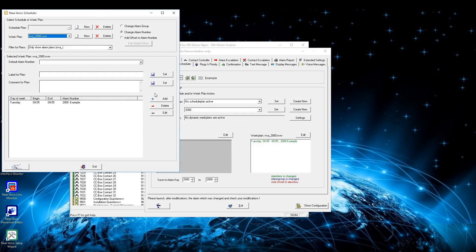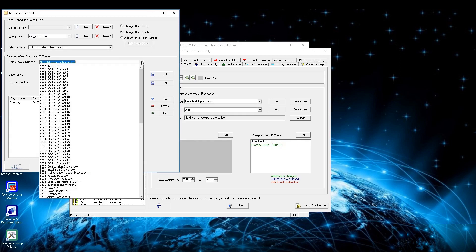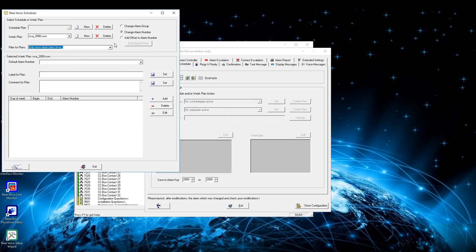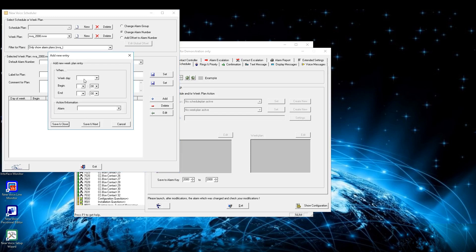On top of this window you can define what should happen — either the group changed for this alarm, the alarm number changed, or an offset added to the alarm for launching. By the drop-down menu default alarm number you can define what alarm number should be launched if the scheduler does not match. Below, a label and a comment can be given for this plan, though these have no functional purpose. By pressing the add button a new entry can be defined — choose your weekday and define the time of the scheduler.